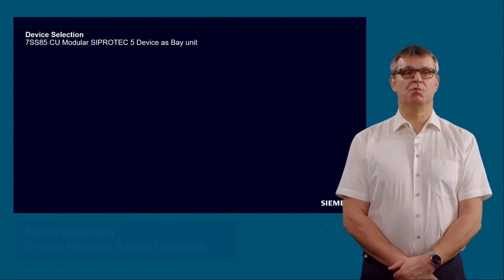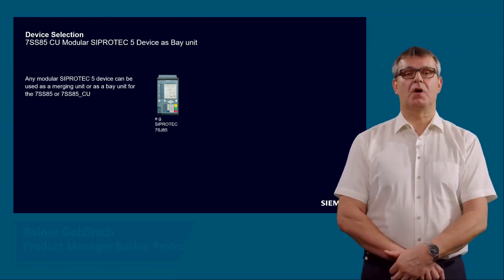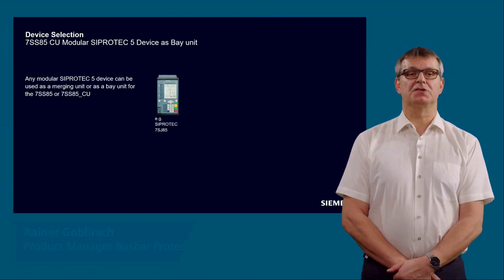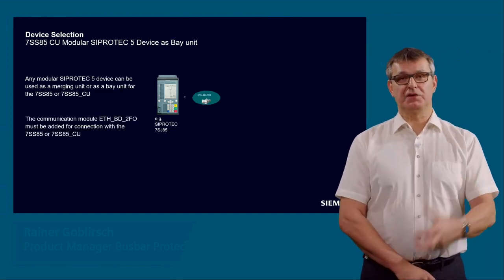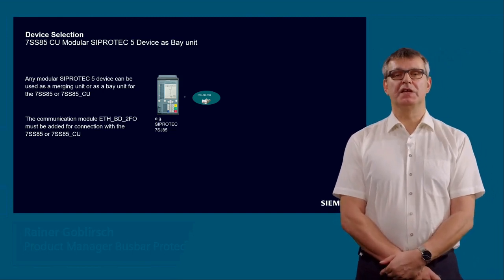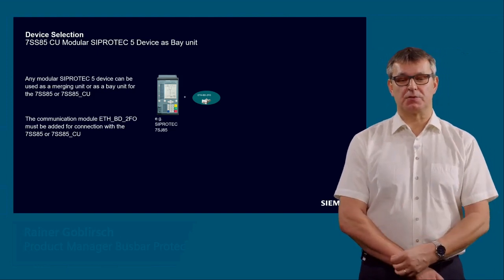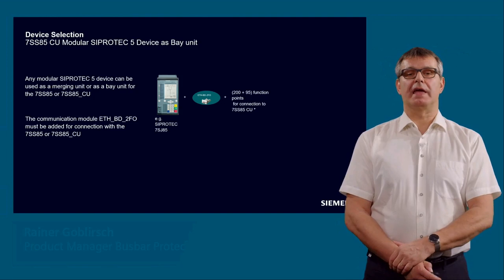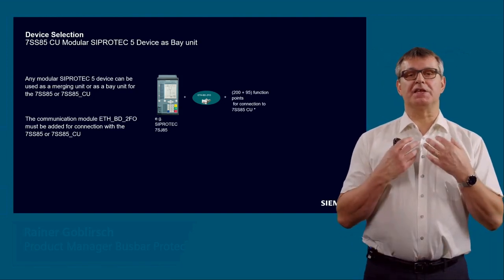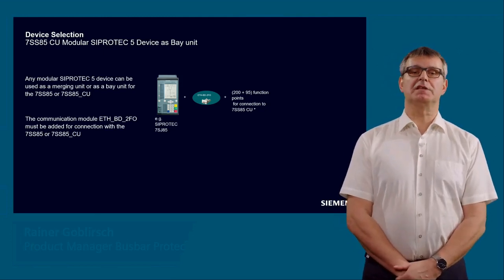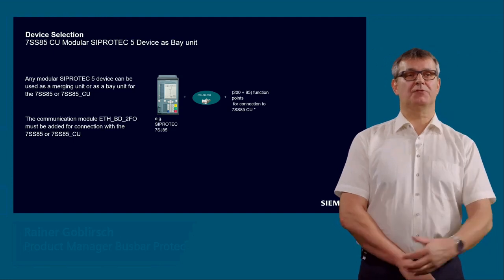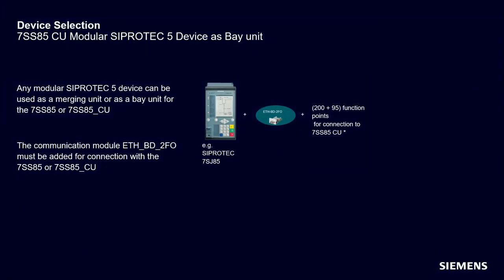As already said, in the 7SS85 each modular SIPROTEC 5 device can be used as a bay unit for the distributed busbar protection. So here in this example, I am using a 7SJ85. And what we need, of course, is communication for the distributed busbar protection. For this communication, we add this Ethernet module. To activate the process bus functionality in general in a modular device, we have to pay 200 function points. And for the special communication to a 7SS85, we have to add a further 95 function points.